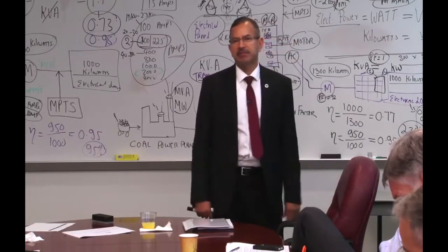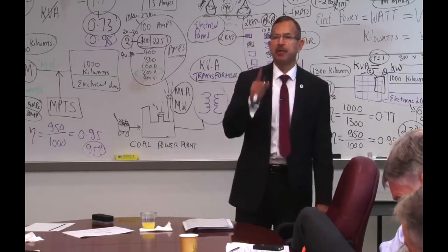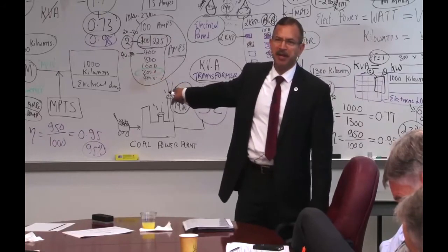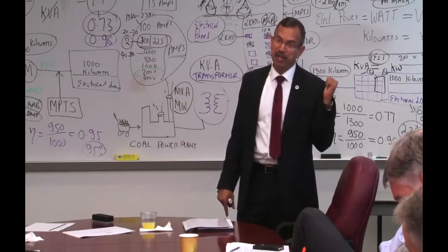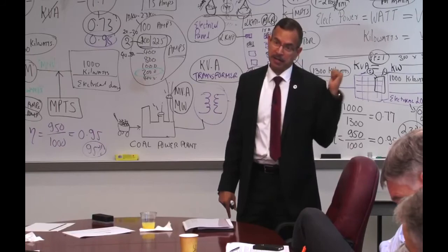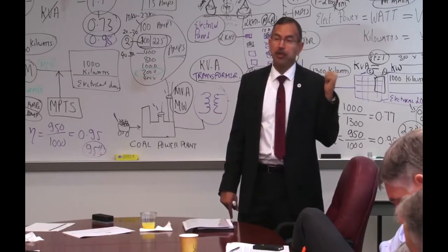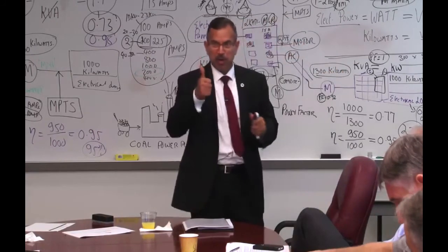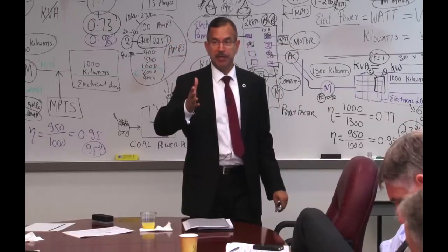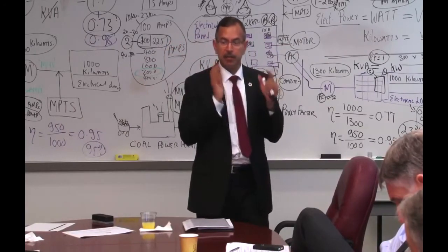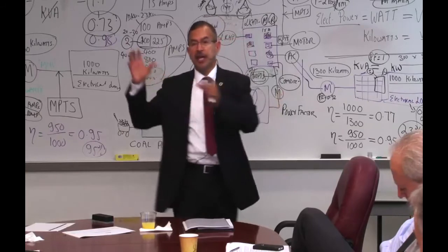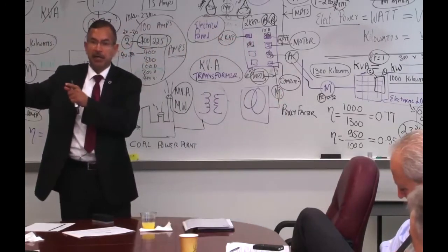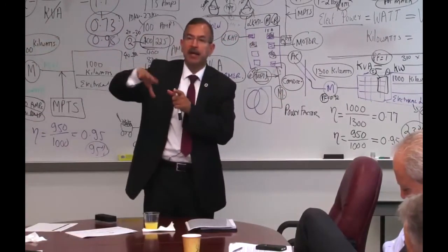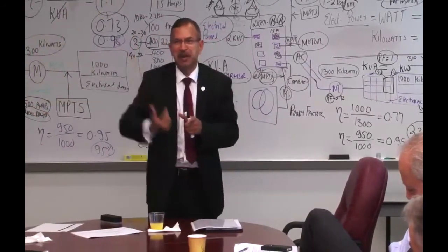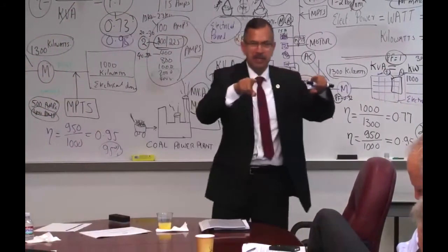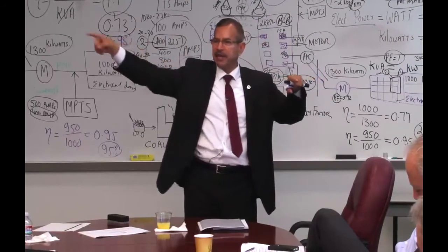Doesn't matter. Because if you have 0.85 upstream at the meter, that means you have 0.4 and 0.2 and 0.1 power factor at the downstream. So you ask me what is a quick thumb rule, where do we put this MPTS unit? If you see one panel which is 0.85, or if you see a main distribution panel, actually on the main panel, if you're 0.95, it is actually better. Because every amp you save, you're saving 0.83 kilowatts of power.